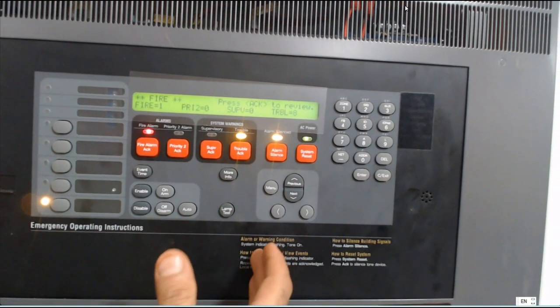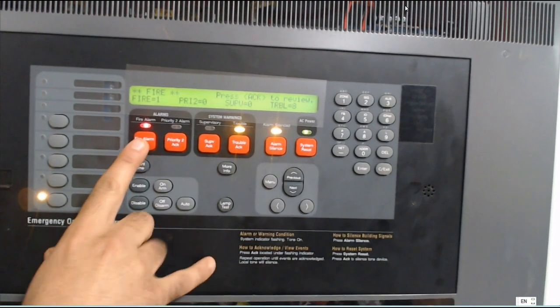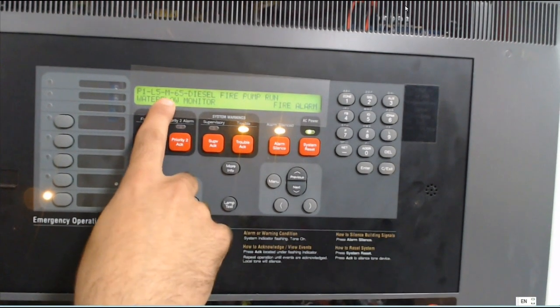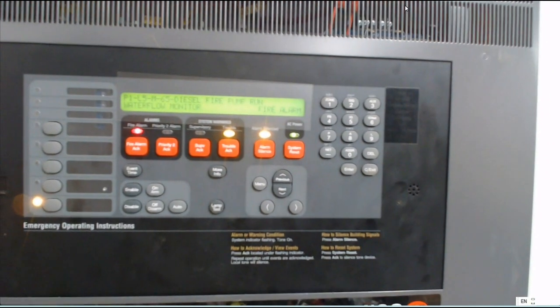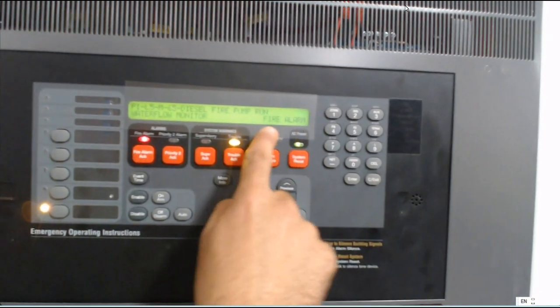Once a fire alarm activates, this fire alarm ack shows. Here it shows panel one, loop five, M means motor module, device number 65 — diesel tank fire pump run. Because the fire pump started, it will show fire alarm.